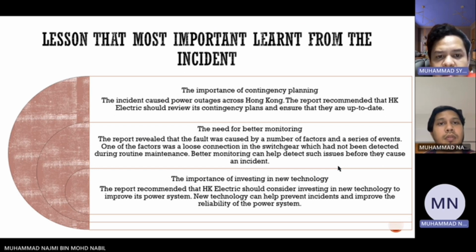The report revealed that the fault was caused by a number of factors and a series of events. One of the factors was a loose connection in the switchgear, which had not been detected during routine maintenance. Better monitoring can help detect such issues before they cause an incident. And number three, the importance of investing in new technology. The report recommended that HK Electric should consider investing in new technology to improve its power system. The new technology can help prevent incidents and improve the reliability of the power system.